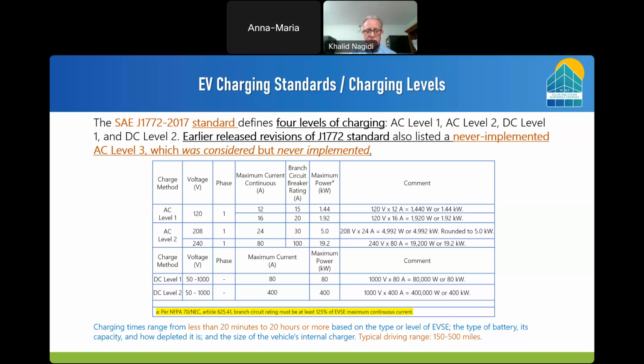As you can see from the bottom in here, the text highlighted in yellow, this is based on North America NFPA, specifically NEC, standard article 625.41. The branch circuit has to be sized at least 125% of the maximum continuous current. In this case, if we go to AC level 1 on the left-hand side at 120 volt, single phase, you have 2 options in here. If you have a circuit breaker of 15 amps, the maximum continuous amps that you can draw to charge your vehicle with level 1 is 12 amps. If you have a 20 amps circuit breaker, the maximum continuous current that you can draw is 16 amps.